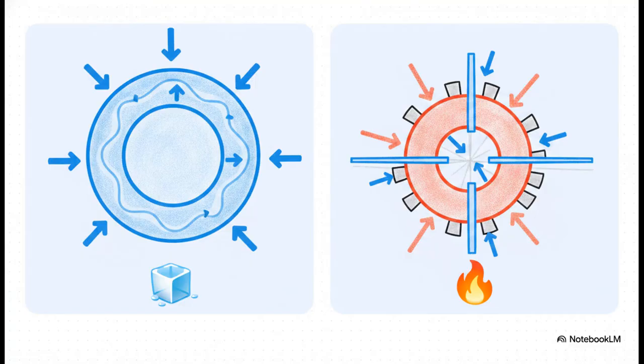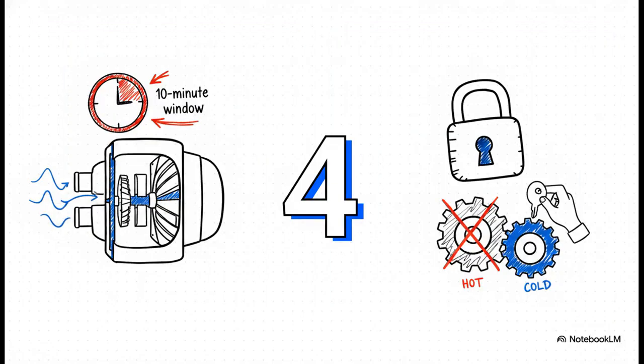You know, the absolute most expensive mistake you can make right after a high-powered trip basically comes down to the physics of how things cool off. Think about it. After a trip, that thin outer casing cools down and shrinks really, really fast. But the heavy, thick rotor core spinning inside stays glowing hot and expanded for way longer. And that mismatch in cooling rates causes the internal clearances between your blade tips and the casing to shrink up dangerously tight.